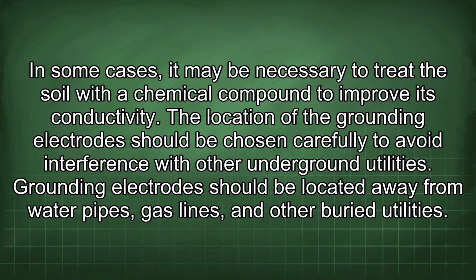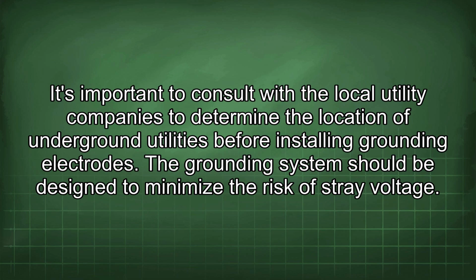The location of the grounding electrode should be chosen carefully to avoid interference with other underground utilities. Grounding electrodes should be located away from water pipes, gas lines, and other buried utilities. It's important to consult with the local utility companies to determine the location of underground utilities before installing grounding electrodes.